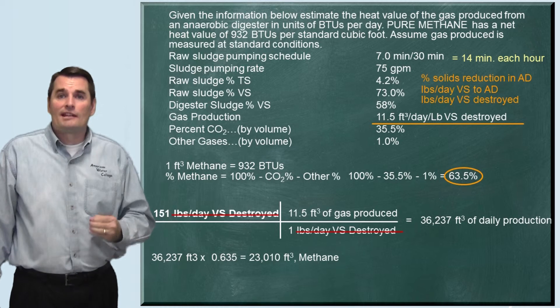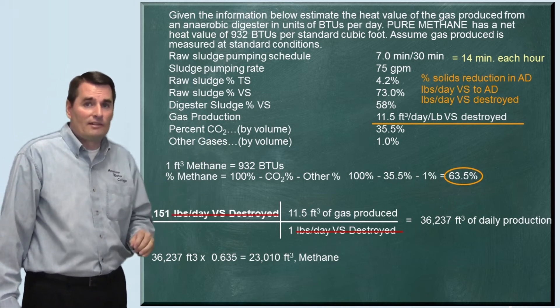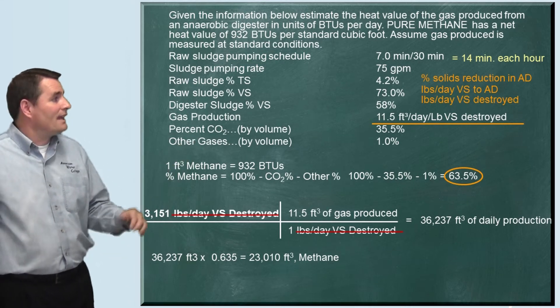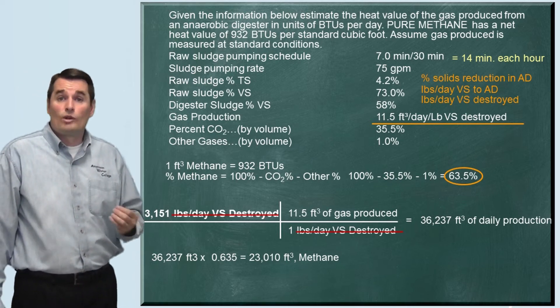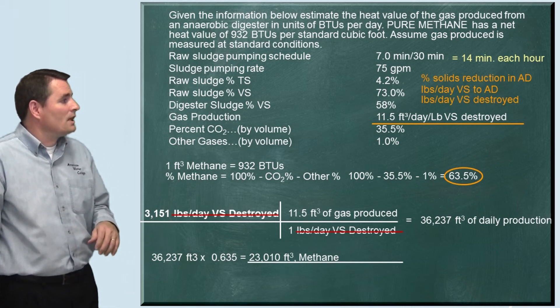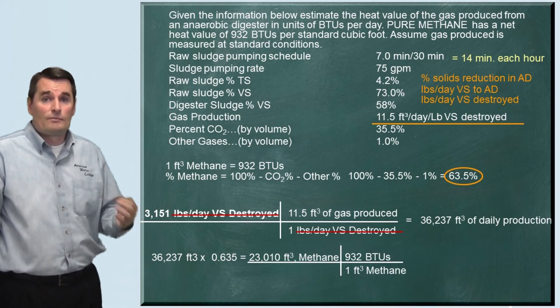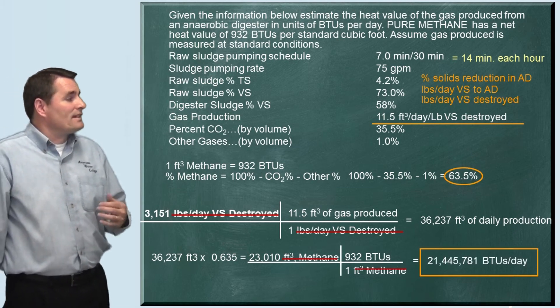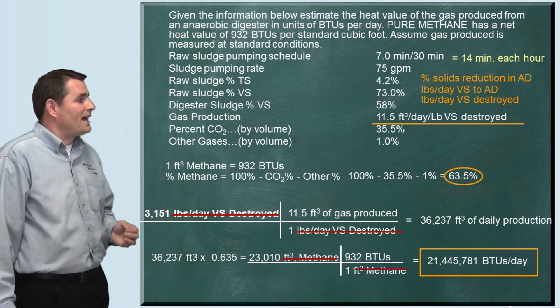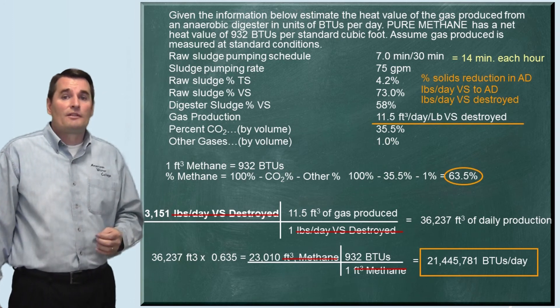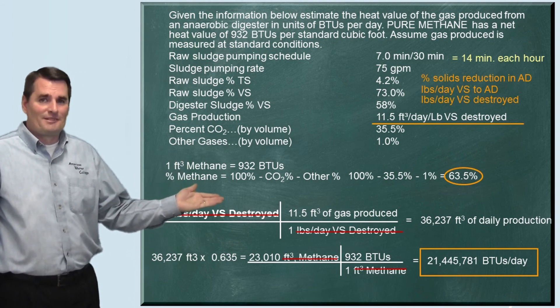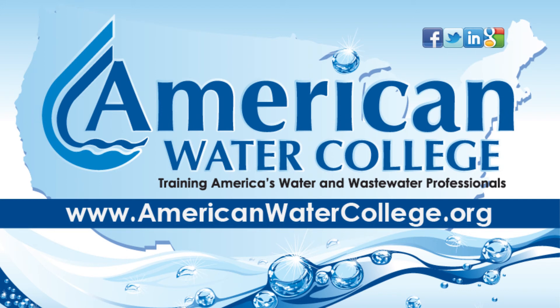Now we know how much methane is produced each day. We just need to convert this to a heat value. Since every cubic foot of methane has 932 BTU of heat value, we take 23,010 cubic feet of methane and multiply by 932 BTU per cubic foot. The result is 21,445,781 BTU per day — and that is how this problem is solved.